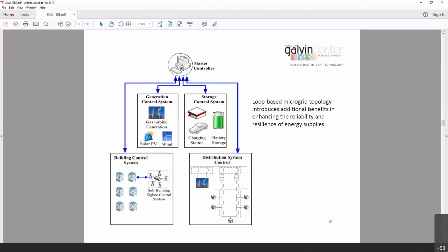It does day-ahead scheduling, figuring out for every hour in the next day the best way to manage the grid: whether to import power from the local distribution system, turn on local generation, how much solar and battery we have, when to charge and discharge batteries, and whether we can do demand response in individual buildings. All that is decided in the day-ahead plan, and also in real time, we make corrections every 10 minutes.